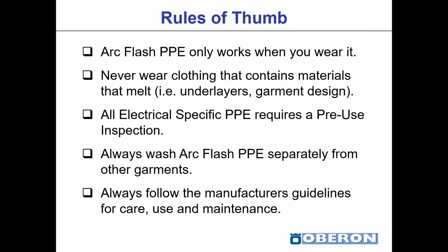The rules of thumb when you're using arc flash PPE is that it only works when you wear it. It's kind of obvious, but it needed to be said. Never wear clothing that contains materials that melt, such as your underlayers or garment design. A question I had just recently from one of my customers was, what about your outerwear? We're moving into the winter months, and questions come up about winter jackets. If I have on my proper arc-rated PPE, such as my coveralls, balaclava, arc-rated face shield, and hard hat, and we need to layer up for some warmth, what type of jacket should we be wearing? Well, the standards such as the NFPA 70E and CSA Z462 identify that the outerwear, so a jacket or a parka, must also be arc-rated. We don't want to be wearing just a regular jacket over top of our arc-rated clothing ensemble.